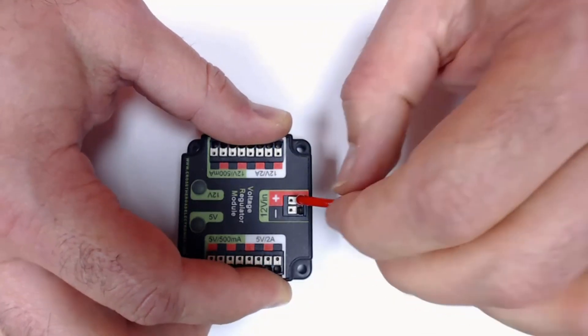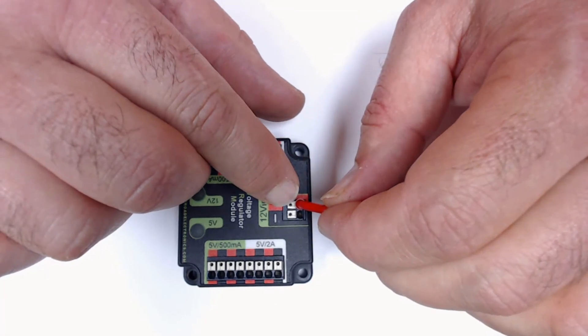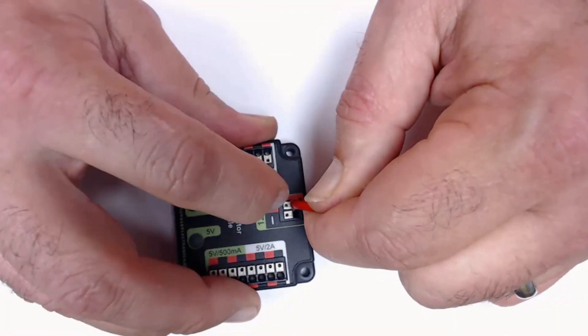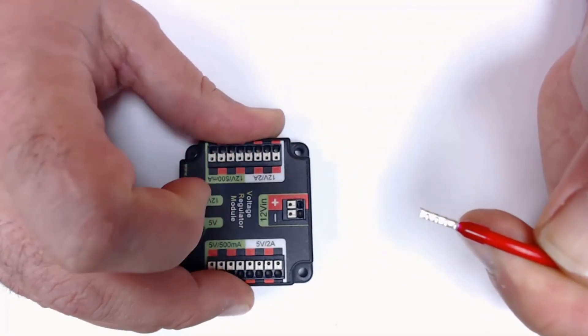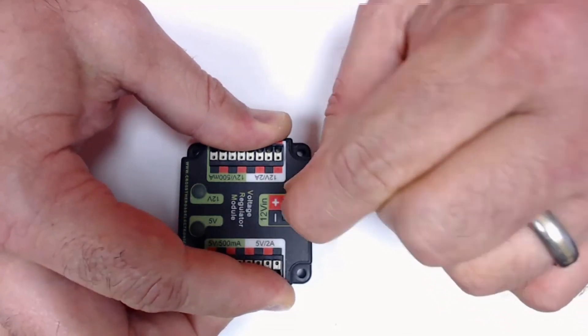And if it's too big, if the diameter of this ferrule is too large, what will happen is it may insert okay, but when you go to pull it out, it will pull right out because this button will stay depressed. And that's not good. So we want to make sure it goes in cleanly, but we also want to make sure it doesn't pull out.